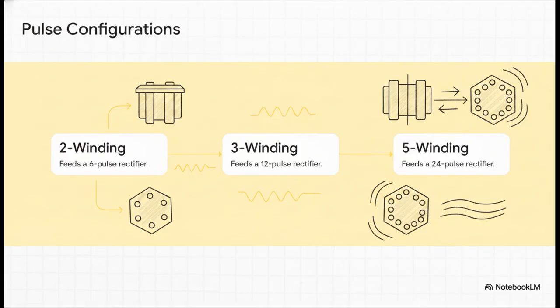So looking at our first design axis, the windings, we can use a pretty simple visual rhythm to see how this scales up. A basic 2-winding transformer feeds a standard 6-pulse rectifier. Step that up to a 3-winding transformer, which has 2 secondaries phase-shifted from each other, and boom, you can feed a 12-pulse rectifier. That harmonic cancellation starts happening just through that phase shift alone. Take it all the way up to a 5-winding transformer, and now you're feeding a massive 24-pulse rectifier.